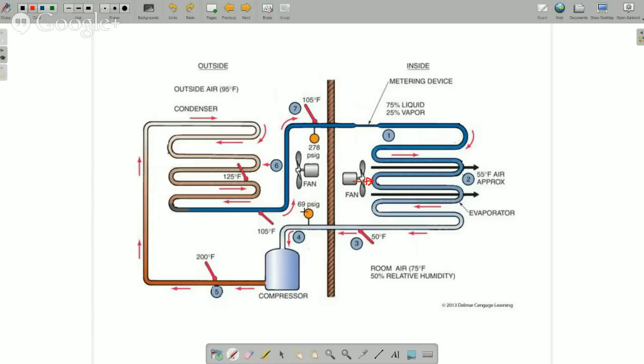All right, so what happens is that refrigerant does not back up and doesn't pick up enough subcooling. And I remember when I first learned subcooling, it was hard for me to get my head wrapped around superheat and subcooling. Just remember that refrigerant backs up and spends more time in the condenser, and it has more time to get rid of heat, and that's how we get our subcooling. But when we have a low system charge, the refrigerant doesn't spend a lot of time in the condenser, and we have very low subcooling.